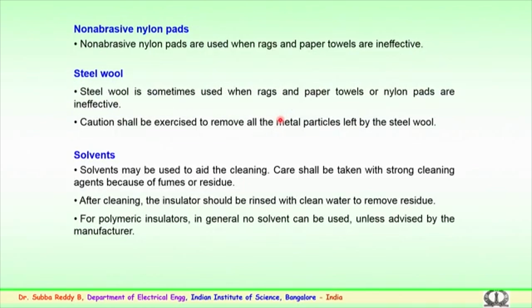Again, various types of equipment and materials are being used. We will look into some of the utilities where they use various methods for cleaning. We go for non-abrasive nylon pads, which are used when cloth or paper towels are ineffective, in case the hardness on the insulator surface is difficult to clean with normal cloth or paper towels. In such cases, non-abrasive hard nylon pads are employed by utility personnel to remove hardened pollutants on the surface of the insulators or bushings, and the contaminants or deposits.